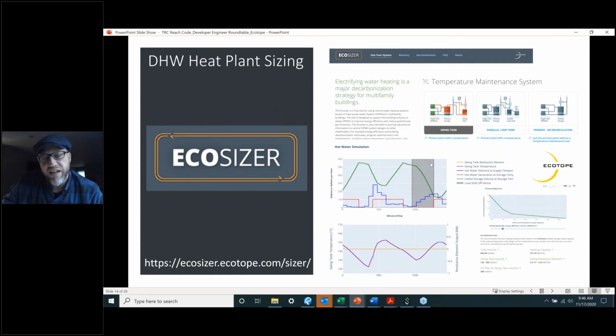We've got this shaded out area, that's our load shift. If you look at the red, that's when we're not running. This shaded area is the part we want to load shift, corresponding to the peak rates inside utilities. We can also model the swing tank in this program -- you can see the swing tank never drops below 120. This is a tool to help validate your sizing and understand how your system's going to run.